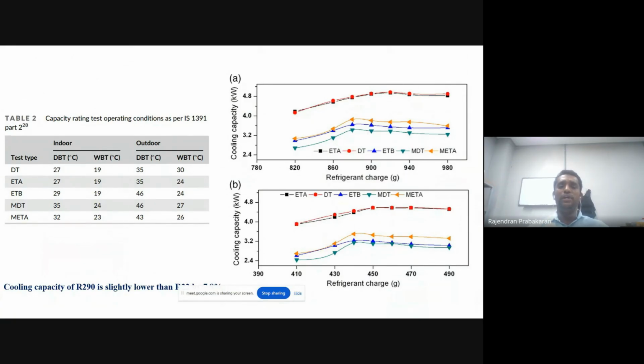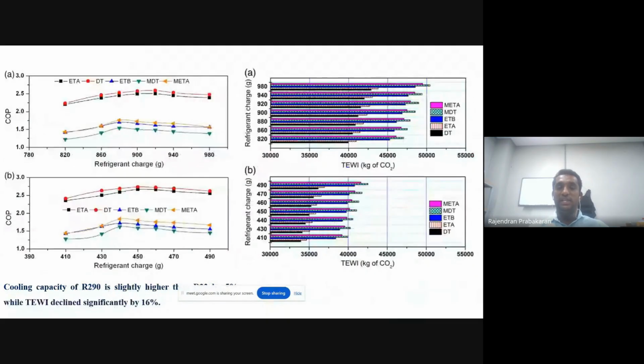conditions. So according to all these conditions, we can see that the cooling performance of R290 is slightly lower than R22. But on the other hand, it has really good COP, about 7% higher. This is majorly because when we are retrofitting R22 with R290, this refrigerant's liquid density is much better, so the refrigerant charge is almost 50%, half of the R22, and it also consumes less power. So because of less power consumption, it showed better COP.